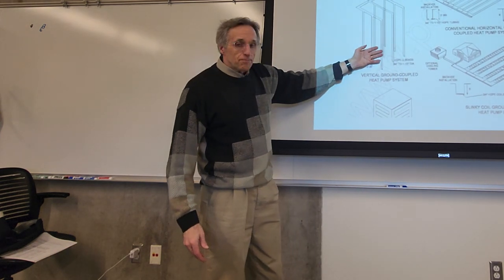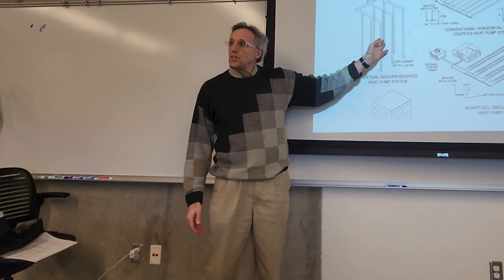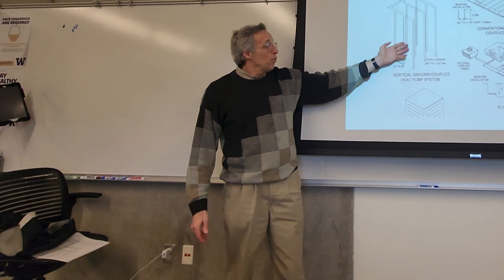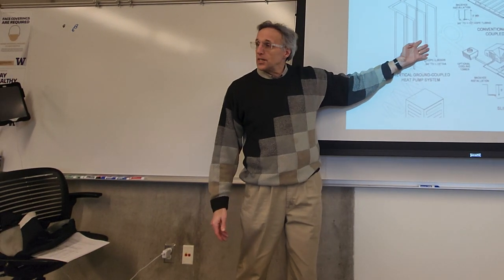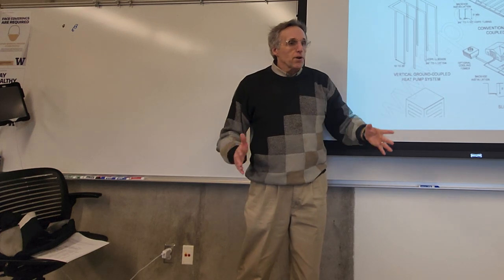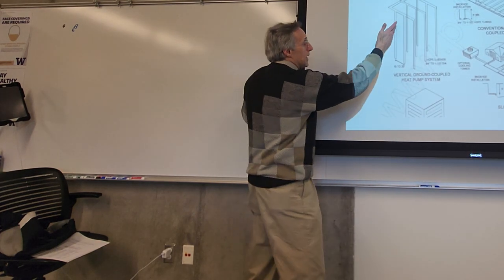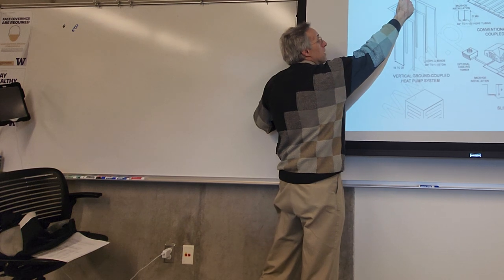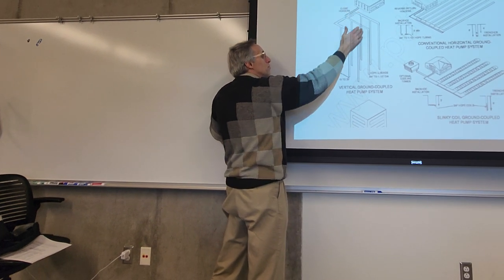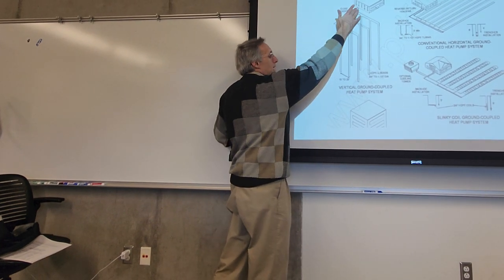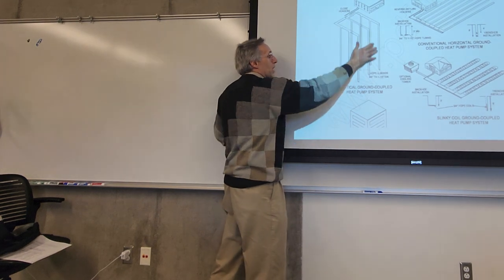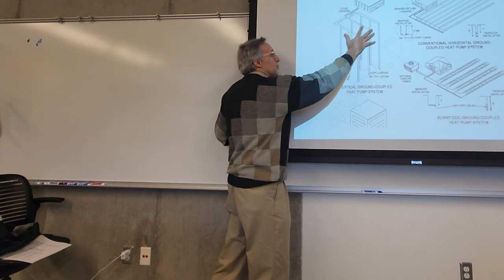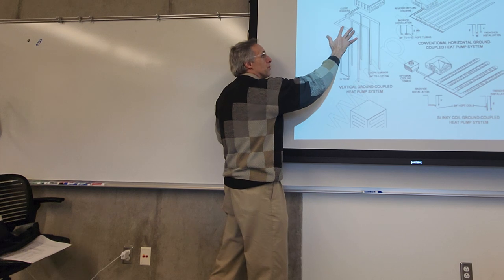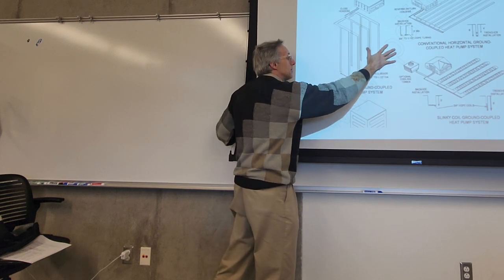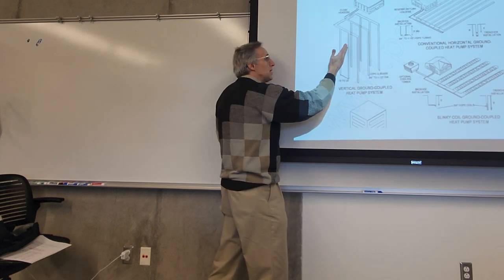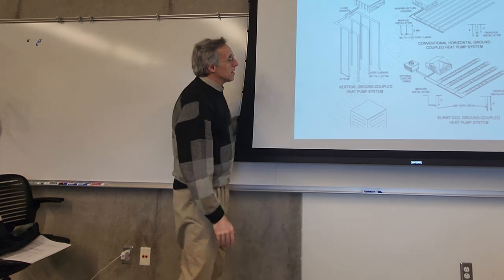Now, in most situations, this would be an antifreeze solution, because you don't want to use just water because it could freeze. So you use some kind of a water antifreeze mix, and it's just moving between the refrigerant, moving between the unit in the house and the ground. It's just going round and round. And so you want lots of surface area so the fluid can give up heat or receive heat as needed.